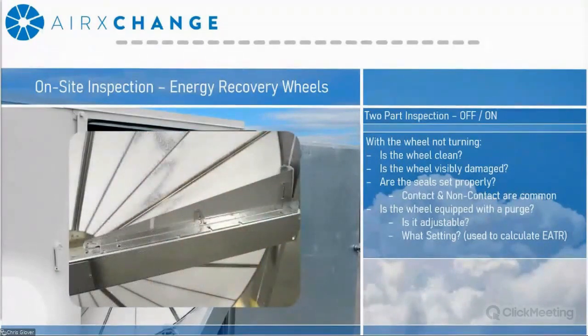You're going to want to check to see if the seals are set properly. Once again, you can use that flashlight method, and you're going to want to follow the manufacturer's suggested method for setting seals. The two most common seals on the market are contact and non-contact seals. Take note of which one you have and make sure it's set appropriately. And lastly, you're going to want to check to see if your device has a purge. A purge is what I'm showing in this picture over here, but it's a mechanical wedge. And it's really there to help minimize leakage in certain situations where there's significant carryover.